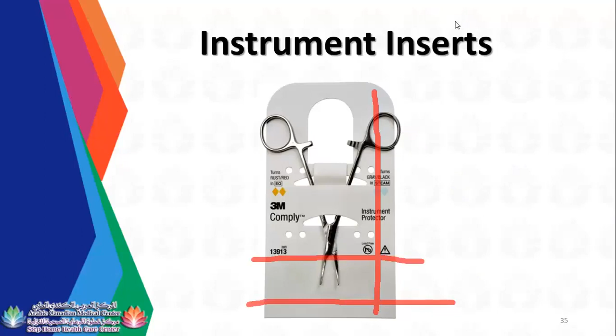For chemical indicator, you need to check there are class 5, class 6 and class 4. Those three are the commonly used chemical indicators in CSSD, but preferably it's class 5 or 6. But if the item is not critical, then they can use the class 4. If it is critical or implants or surgery, then they need to use the class 5 or 6. Okay?